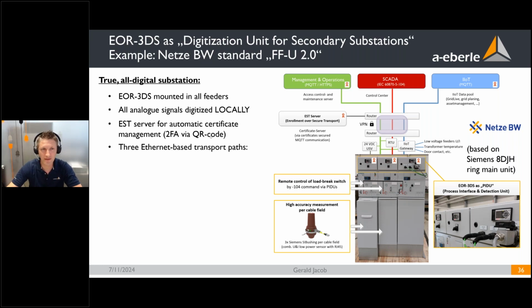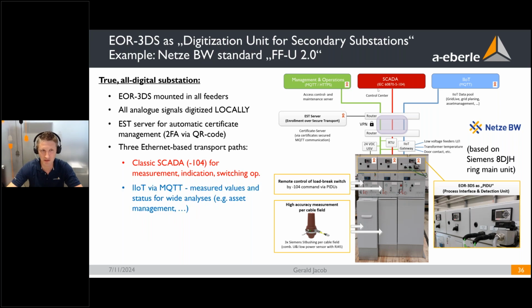What else we can see here, and that is what I want to emphasize especially on this page, are the 3 Ethernet-based protocols. Each device communicates to all of these 3 heads. To the central SCADA system via 104 protocol to the control center: here the measurements, the earth fault and short circuit indications are transmitted, as well as, in command direction, the switching operations. Then we have the second path, the blue path. This is IoT or IIoT, Industrial Internet of Things. So this is not in the cloud, not in the internet. This is locally installed on premise, in the network of Netze BW, but they wanted to have a separate access for grid planning and asset management, where they can subscribe to all these different data out of these secondary substations.